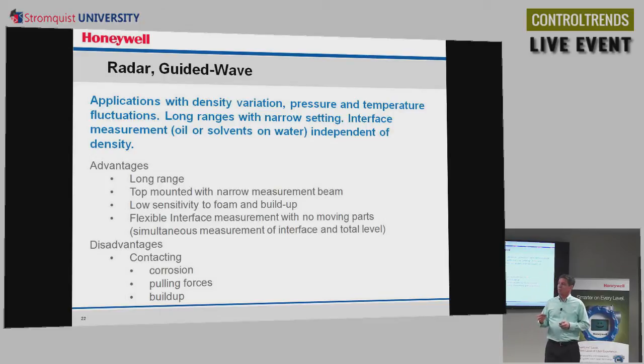Guided wave is also very good for interface measurement. These other technologies really don't work so well for interface. You can do interface measurement with differential pressure, with the capacitance type, but it just doesn't work quite as well. In the case of differential pressure, you have to maintain a certain height in your tank, the surface height, to measure the interface. So if that height remains the same, then the interface between the two liquids changes, and you can measure that. But to be able to do that, this surface level has to be kept the same, and that's not always easy to do. With guided wave, you don't have to worry about keeping that surface the same.